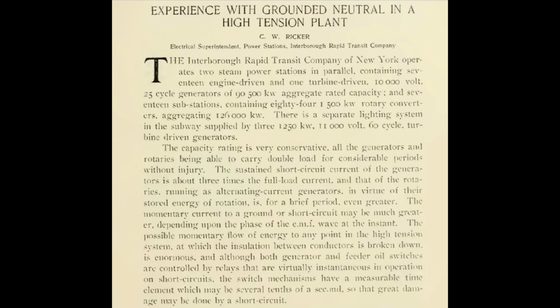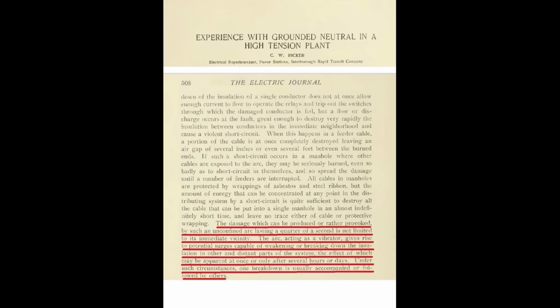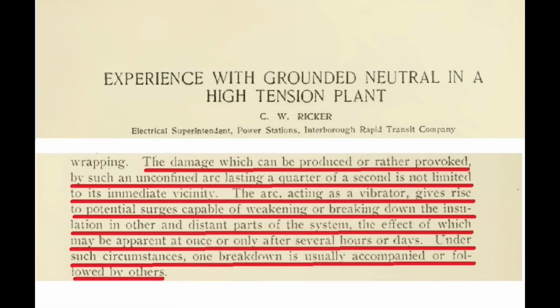Another article in the same publication, Experience with Grounded Neutral. We can see, on page 508, that engineers began to realize that the damage which can be produced, or rather provoked, by such an unconfined arc lasting a quarter of a second was not limited to its immediate vicinity. The arc, acting as an oscillator, gives rise to potential surges capable of weakening or breaking down the insulation in other distant parts of the system, the effect of which may be apparent at once or only after several hours or days. Under such circumstances, one breakdown is usually accompanied or followed by others. But this was only the beginning. Much more work was needed.